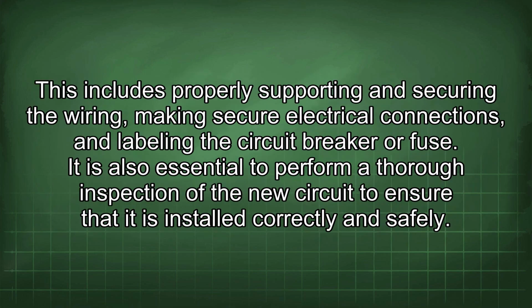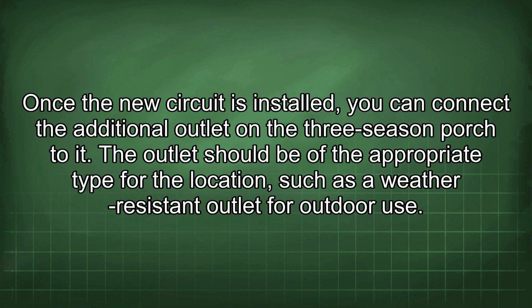Fifthly, you need to install the new circuit in accordance with the NEC and any local codes. This includes properly supporting and securing the wiring, making secure electrical connections, and labeling the circuit breaker or fuse. It is also essential to perform a thorough inspection of the new circuit to ensure that it is installed correctly and safely. Once the new circuit is installed, you can connect the additional outlet on the 3-season porch to it.